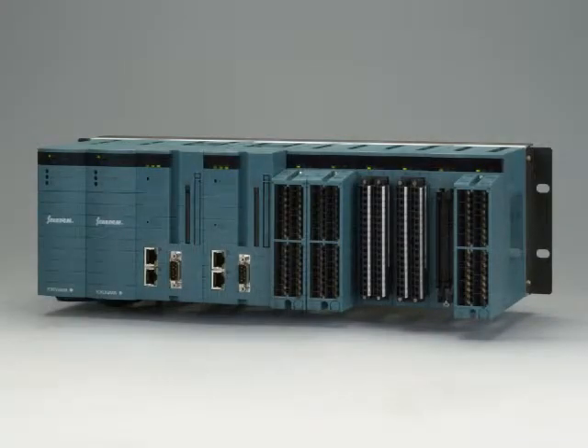Second is FCN. It is a 19-inch rack-mountable controller and can be expanded up to three nodes. It can have redundant power supplies, CPUs, buses, and some IO cards, such as Foundation Fieldbus cards. Each CPU has two built-in Ethernet ports, which give the controller great flexibility for network connection. Expandable IO cards and hot-swappable almost all components make FCN a highly reliable, flexible, and powerful process controller.